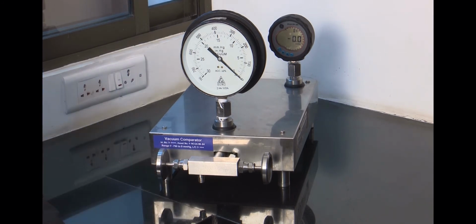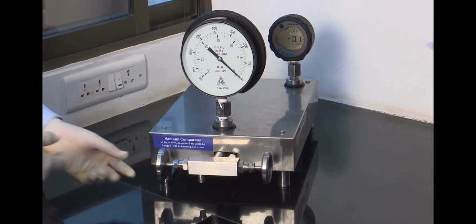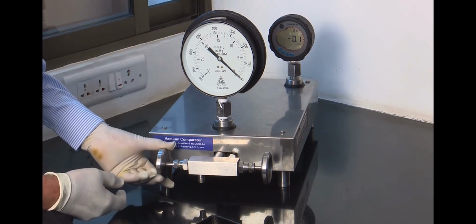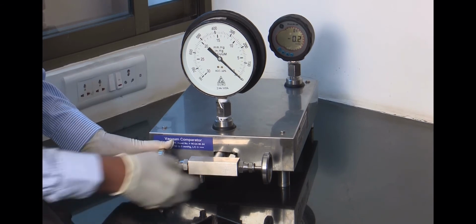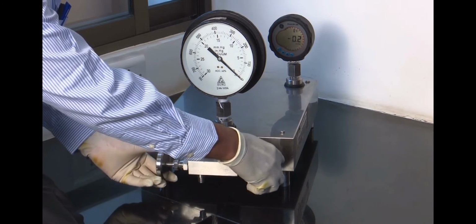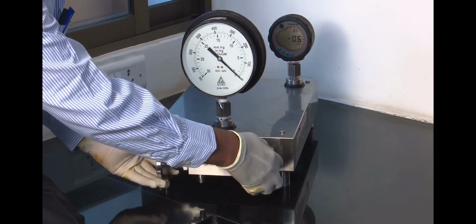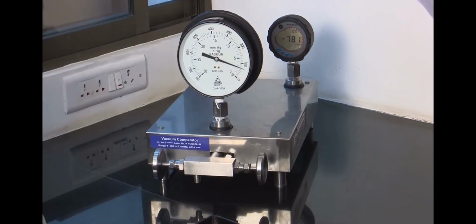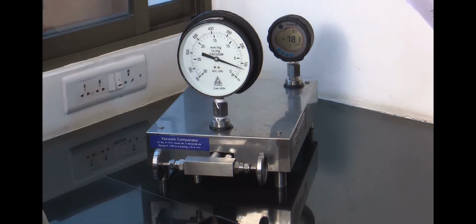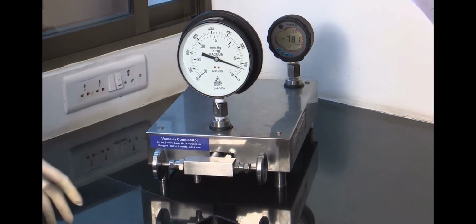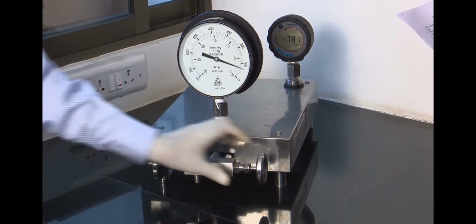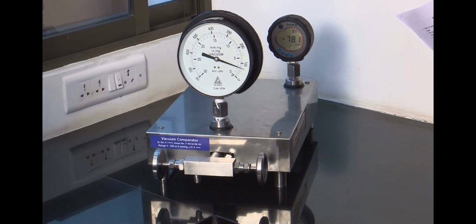Ensure that pointer is on 0. Now start calibration for increasing cycle. Open the regulating valve and set minus 70 mm Hg on vacuum gauge UUC. This is first calibration point. Allow it to stabilize for 30 seconds. Now record the reference standard reading against first calibration point in the worksheet.